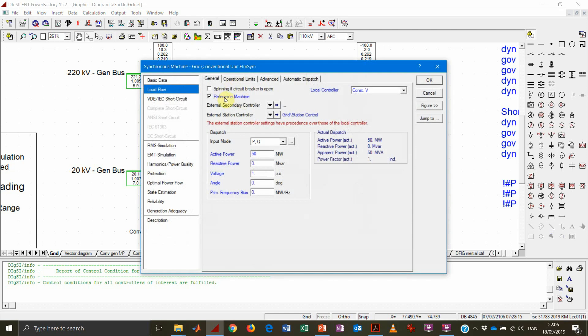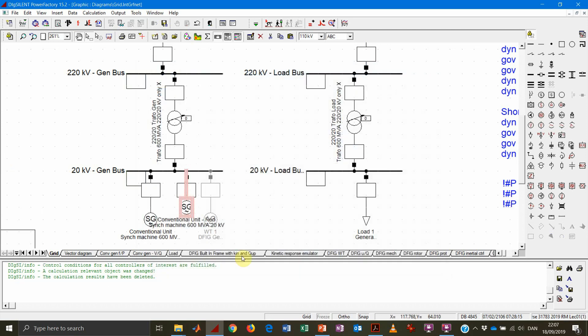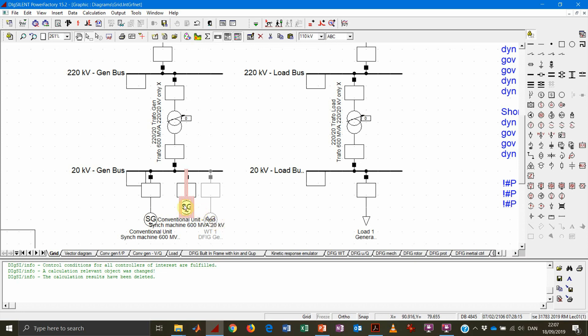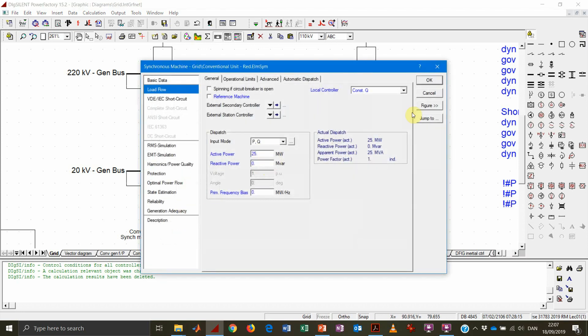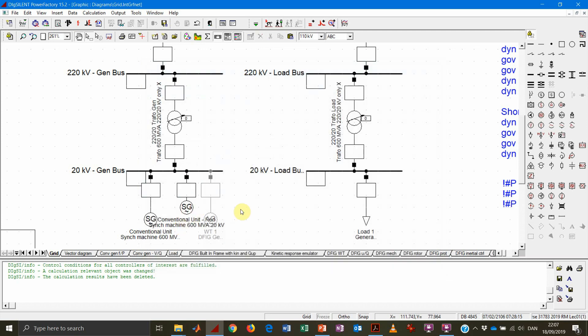We can see that the slack flag appears on the old machine, and also on the new machine, but PowerFactory is of course choosing to ignore one of the two flags. However, at this point, even though we duplicated the generator, the new generator is just a synchronous machine connected to the system — it does not really have any power plant behind it. Even though it is producing 25 MW, it will keep producing that amount regardless of what happens in the system, because there is no device capable of controlling it.